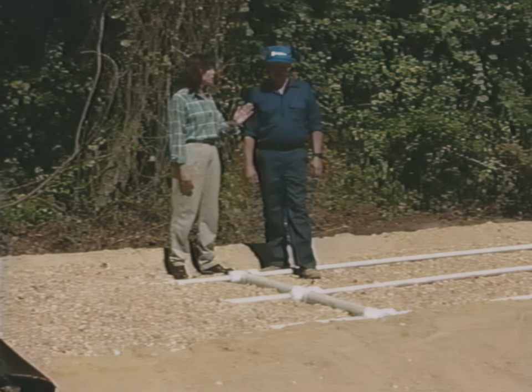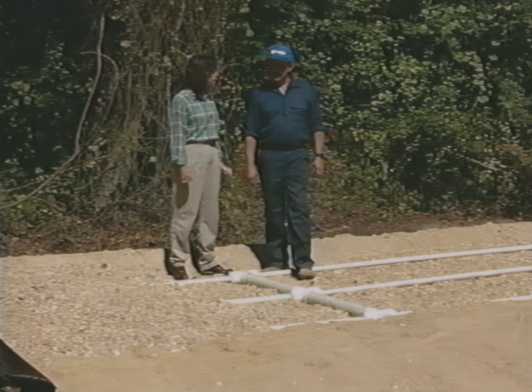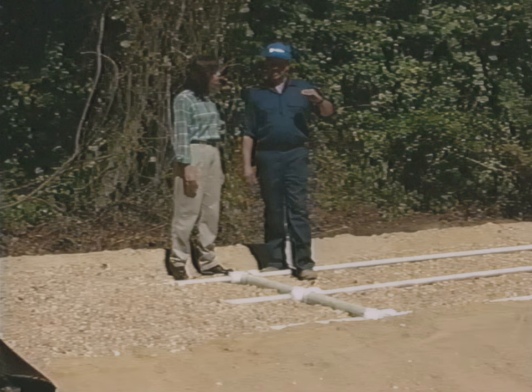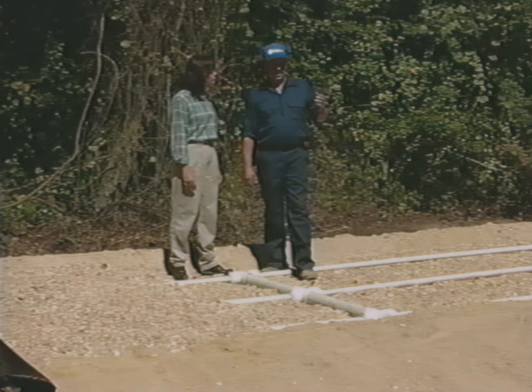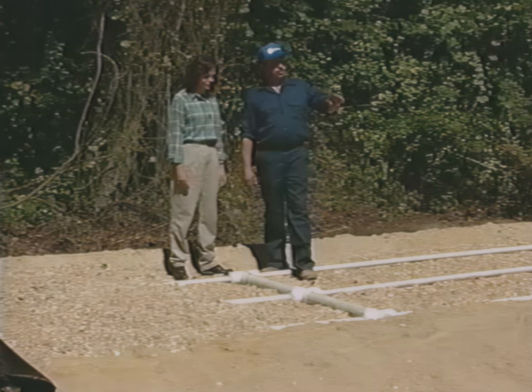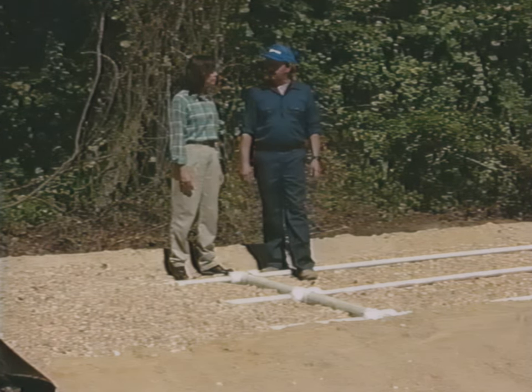And the pump back in the pump chamber has an on-off float so that it isn't running all the time. No — it only runs for a few minutes at a time. We set a float level to turn it on. When the effluent from the septic tank comes to that level, it moves the effluent into the gravel bed, down into the ground, continues pumping until it reaches our off-level, then shuts the pump off automatically.